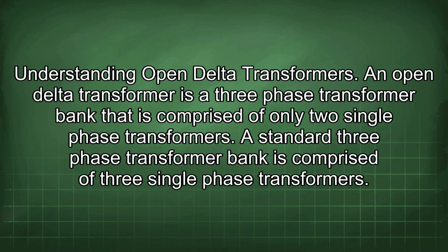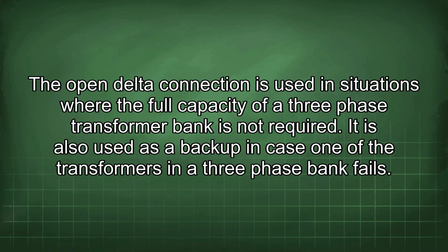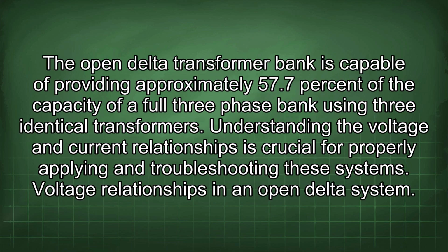Understanding open delta transformers. An open delta transformer is a three-phase transformer bank that is comprised of only two single-phase transformers. A standard three-phase transformer bank is comprised of three single-phase transformers. The open delta connection is used in situations where the full capacity of a three-phase transformer bank is not required. It is also used as a backup in case one of the transformers in a three-phase bank fails. The open delta transformer bank is capable of providing approximately 57.7% of the capacity of a full three-phase bank using three identical transformers. Understanding the voltage and current relationships is crucial for properly applying and troubleshooting these systems.